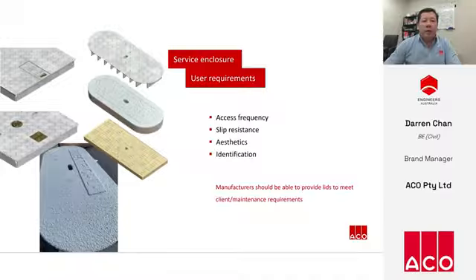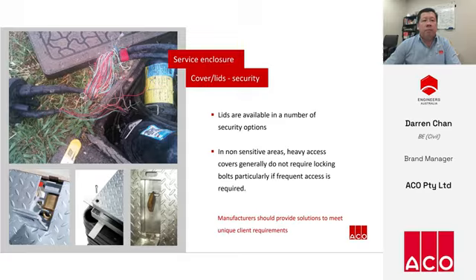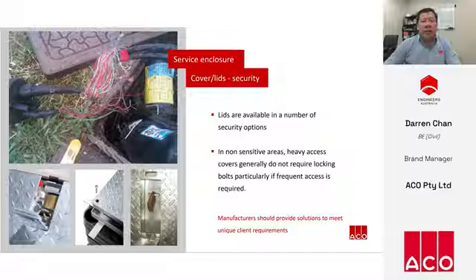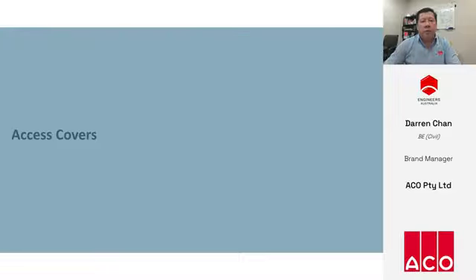Manufacturers should be able to provide lids to meet these project-specific requirements. Depending on the security requirement of the cable route, lids are available in a number of security options: standard bolt, security bolt, padlocks, or high security SCEC padlocks. In non-sensitive areas, heavy access covers generally do not require locking bolts, particularly if frequent access is required. Manufacturers should be able to provide lids to meet the level of security required for your project.